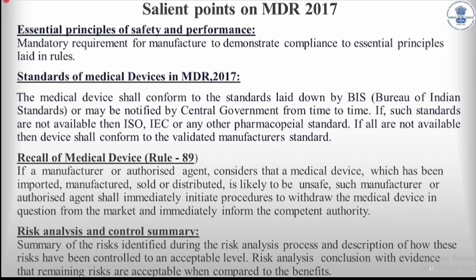So next, a key point on recall of medical devices. This is specified in rule number 89. If a medical device which is manufactured or authorized for sale in India has reasonable reasons to believe it is unsafe, then such manufacturer or the authorized agent is required to immediately start the process of withdrawing the medical device from the market and inform the licensing authority regarding the recall of the medical device and the completion of recalling medical devices.